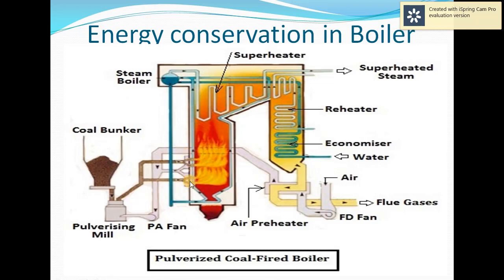Inside the boiler, we have to burn this coal — to do the combustion. For the combustion process, air is required. This is the second circuit: the FD fan (forced draft fan) sucks atmospheric air through a duct and passes it through the air preheater where it gets hot. Hot air is then supplied to the boiler for combustion. Coal and air combine there and a fireball is produced. Heat energy is evolved in this section.